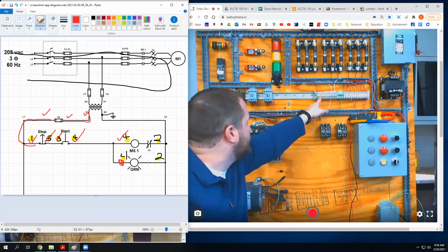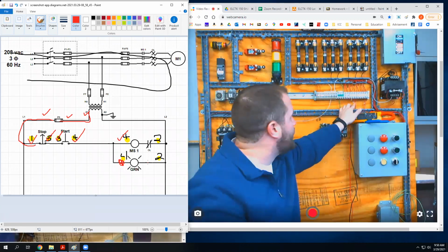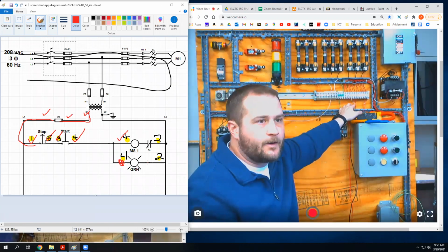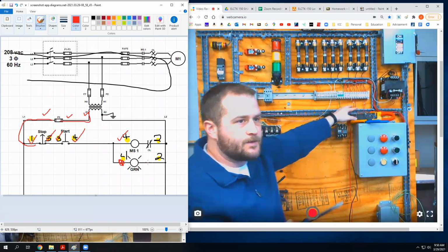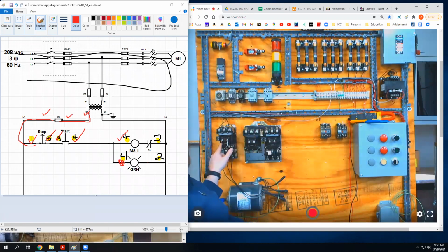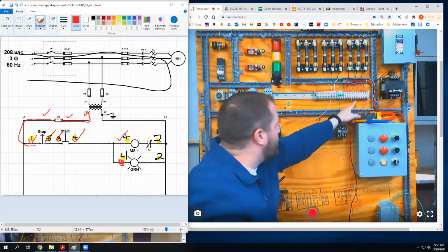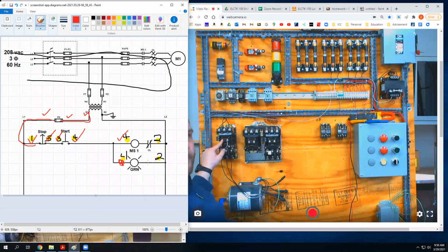What makes the most sense is I have a number 4 right here. And somebody else mentioned that not only is this further away, so you're using more copper, more wire to get there, but this is kind of a smaller terminal right here. This lug is meant to handle more wires. As a rule of thumb, I would always limit your number of wires to 2 under each location if you can.